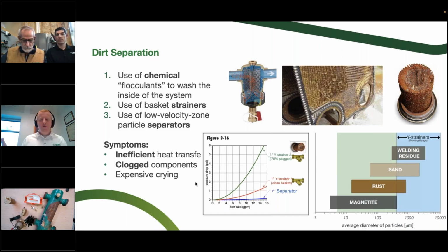And you might even have one in your own home. I mean, you've got an air filter in there. How much air do you think that system is going to be able to flow if the filter's clean versus plugged? And that's the whole idea with a strainer: when it's brand new, that's your best chance for the most flow that you're ever going to get through it. As it starts to plug up over time, your flow rate's going to decrease, or if you've got a variable speed circulator, your current draw is going to go up because it's going to start ramping up on top of it, but sooner or later it's going to plug up.